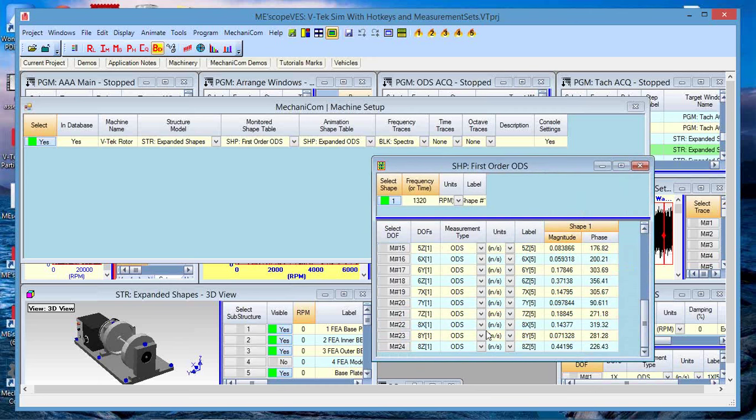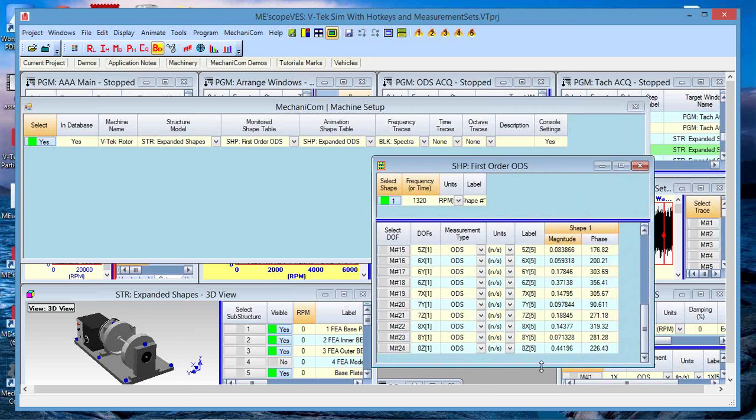And these are the ones that are going to be monitored, these shape components here, to give us the red light, green light indication of whether these 24 degrees of freedom, these 24 accelerometer signals, are actually within our prescribed bounds. You can see the first one going in here is a tach signal. Now that's a little strange. I wouldn't have expected that.